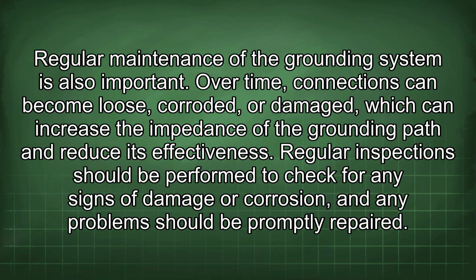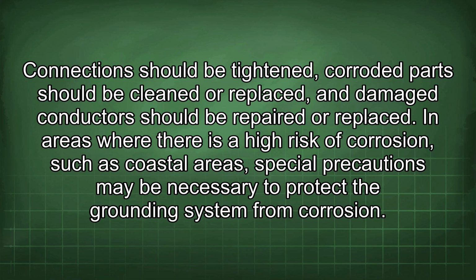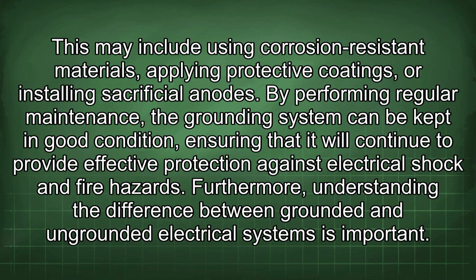Regular maintenance of the grounding system is also important. Over time, connections can become loose, corroded, or damaged, which can increase the impedance of the grounding path and reduce its effectiveness. Regular inspection should be performed to check for any signs of damage or corrosion, and any problems should be promptly repaired. Connections should be tightened, corroded parts should be cleaned or replaced, and damaged conductors should be repaired or replaced. In areas where there is a high risk of corrosion, such as coastal areas, special precautions may be necessary to protect the grounding system from corrosion. This may include using corrosion-resistant materials, applying protective coatings, or installing sacrificial anodes. By performing regular maintenance, the grounding system can be kept in good condition, ensuring that it will continue to provide effective protection against electrical shock and fire hazards.